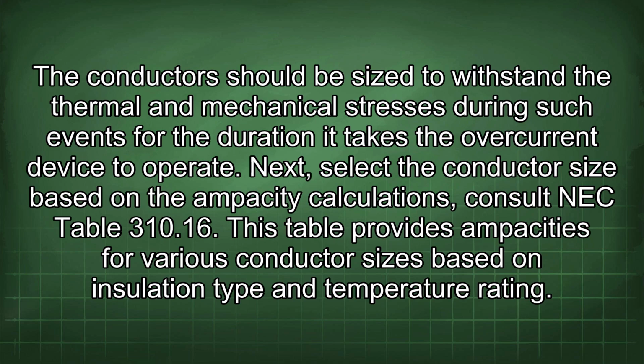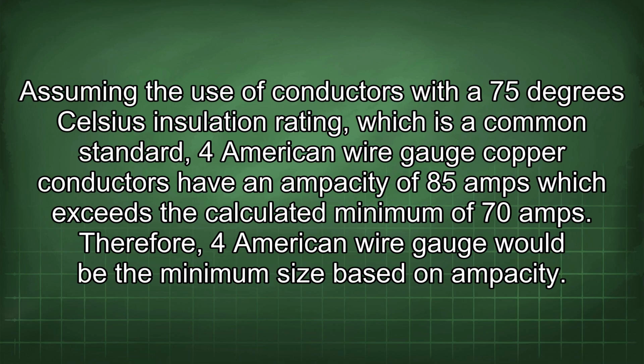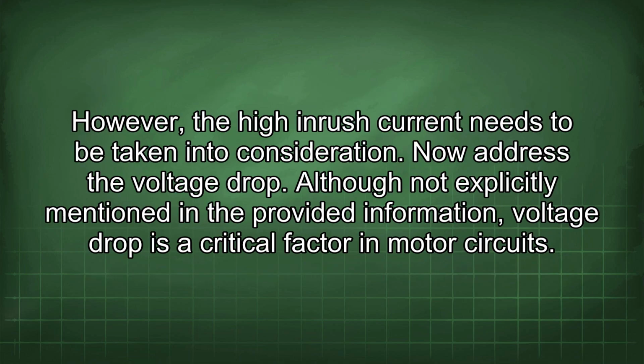Next, select the conductor size based on the ampacity calculations. Consult NEC Table 310.16. This table provides ampacities for various conductor sizes based on insulation type and temperature rating. Assuming the use of conductors with a 75 degrees Celsius insulation rating, which is a common standard, 4 American wire gauge copper conductors have an ampacity of 85 amps, which exceeds the calculated minimum of 70 amps. Therefore, 4 American wire gauge would be the minimum size based on ampacity. However, the high inrush current needs to be taken into consideration.